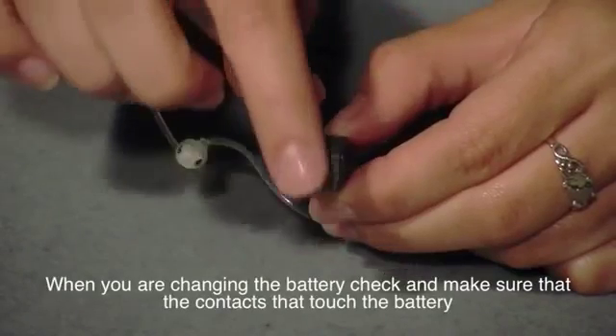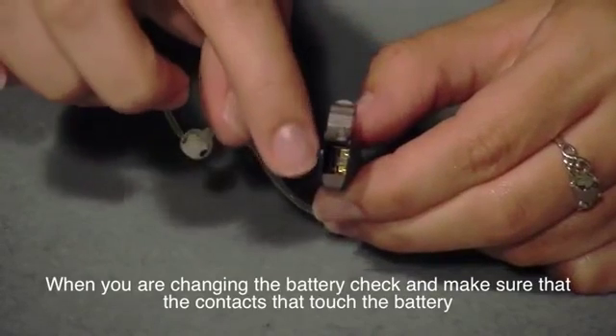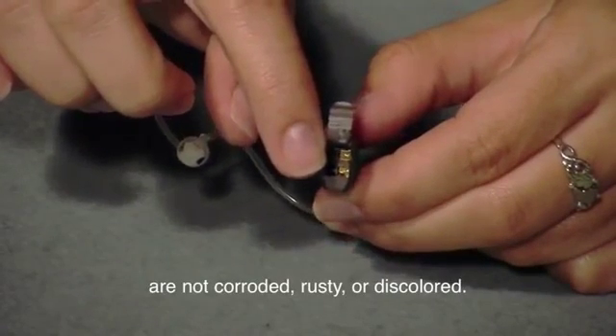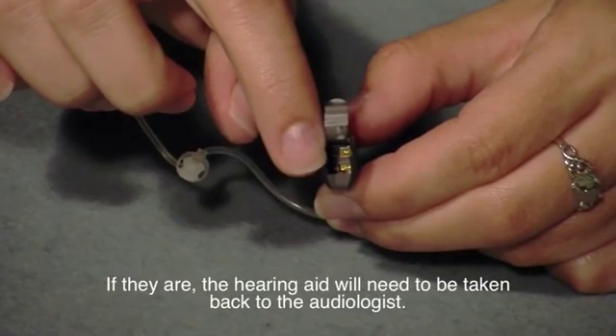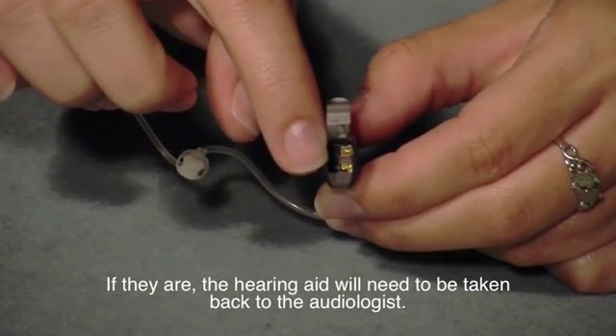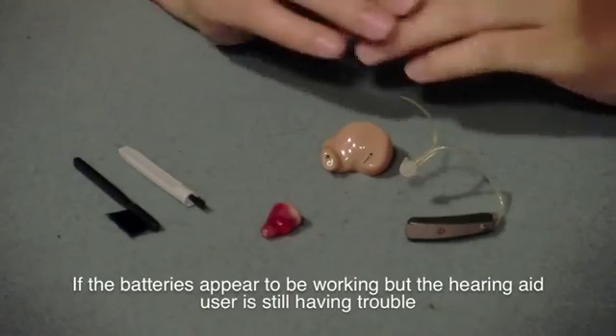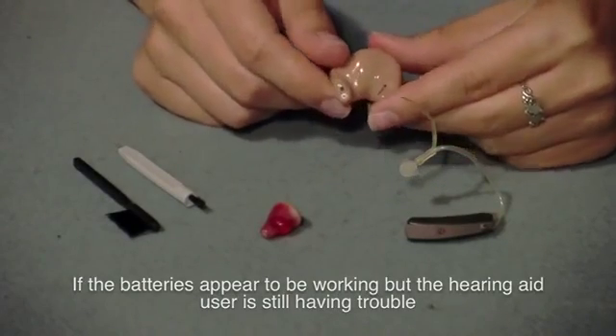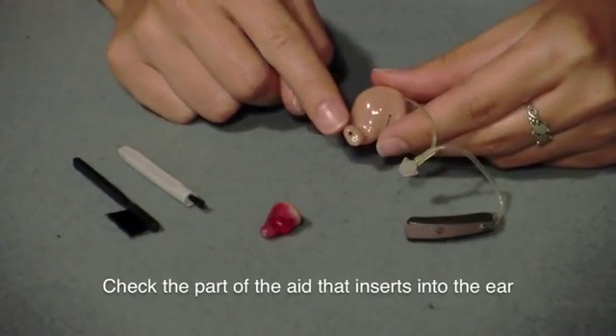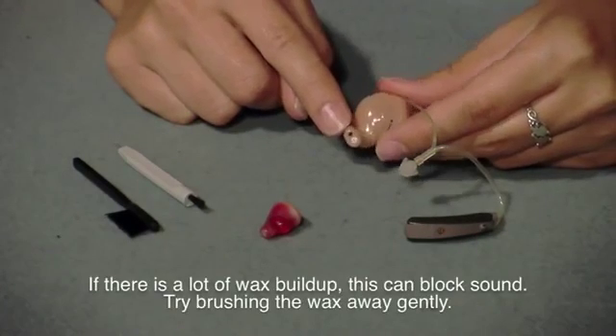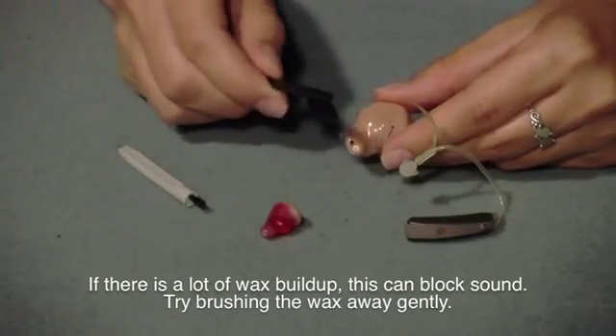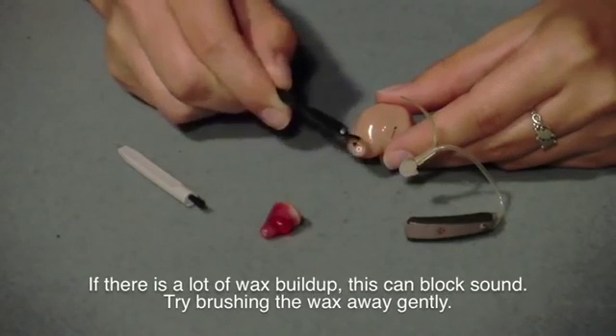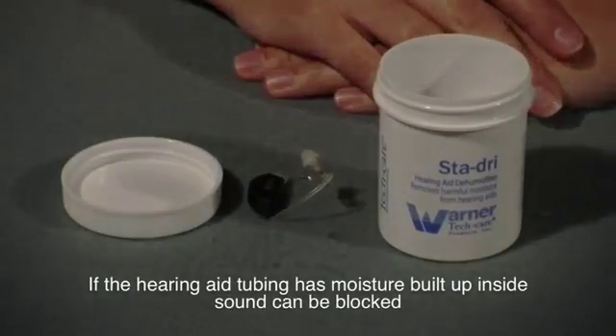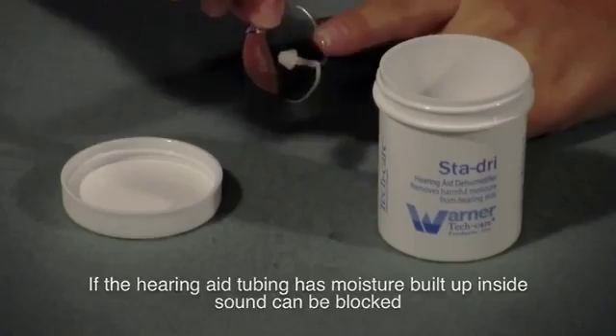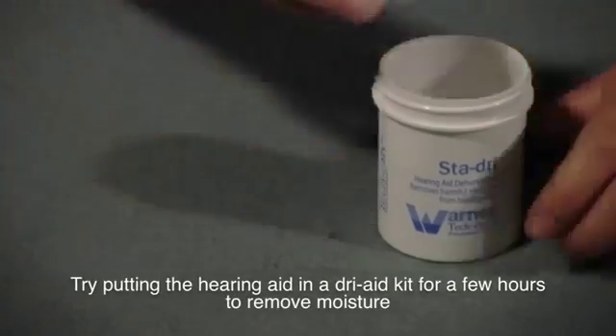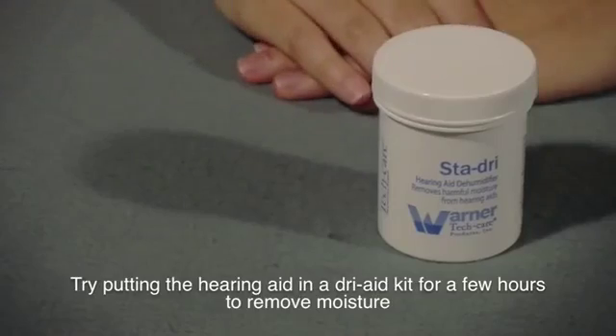When you are changing the battery, check and make sure that the contacts that touch the battery are not corroded, rusty, or discolored. If they are, the hearing aid will need to be taken back to the audiologist. If the batteries appear to be working, but the hearing aid user is still having trouble, check the part of the aid that inserts into the ear. If there is a lot of wax buildup, this can block sound. Try brushing the wax away gently. If the tubing has moisture built up inside, sound can be blocked. Try putting the hearing aid in a dry aid kit for a few hours to remove moisture.